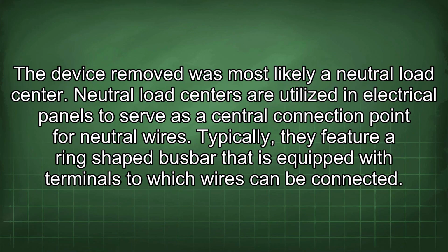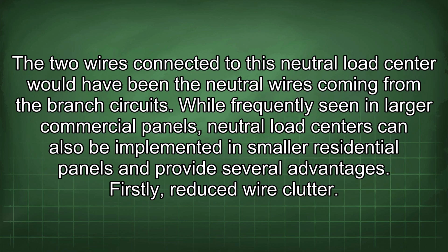The device removed was most likely a neutral load center. Neutral load centers are utilized in electrical panels to serve as a central connection point for neutral wires. Typically, they feature a ring-shaped busbar that is equipped with terminals to which wires can be connected. The two wires connected to this neutral load center would have been the neutral wires coming from the branch circuits.